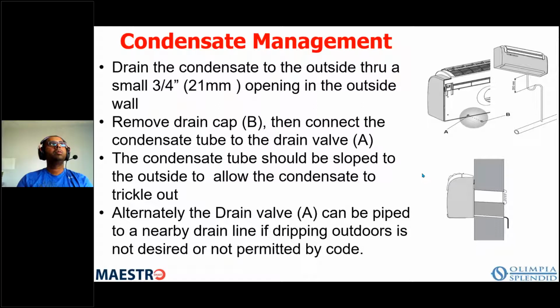So what they would do in the wintertime is they'll take the grill off outside and put this cap in there. And the cap is like, just think of an 8-inch metal cap that you put on the end of a duct. This cap will have 1.5-inch duct board on the inside. So basically when you take the grill off and you put this cap on, you're sealing off both those holes. It's also what we're referring to as a hurricane kit for Florida, because in Florida, if you penetrate the wall for whatever reason, you must have a means of blocking that up during a named storm. So this 8-inch cap with the insulation on the back is absolutely perfect for that application.